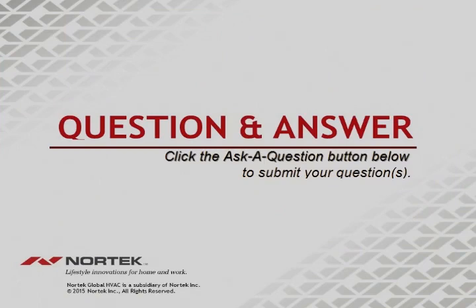Next question. Powered or bypass humidifiers. Okay, that's an easy one. Powered humidifiers, if you can't get them onto the supply duct, powered humidifiers are worthless. All right. Bypass, I like bypass humidifiers because you have the flexibility, obviously. You have the simplification of their wiring and everything else. So I'm always going to recommend a bypass. Powered humidifiers are great as long as you can get them where they're supposed to be. If you can't locate them there, then I can't recommend those. I don't care for those at all.